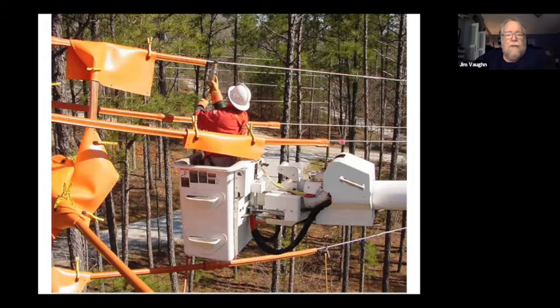The rules say that this part of the conductor, I am not working this conductor. I am working this conductor. This is the conductor that I can leave uncovered while I perform my work. This conductor is not. This conductor, the MAD, starts at the exposure and comes back this way 26 inches, which means that it looks like he's about a shoulder length away from being inside the MAD, which is a violation. Now, if we don't teach this as a way of making our judgments about work positions and what we need to cover, then we're making a mistake.